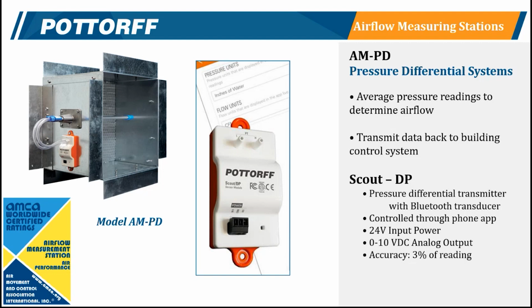So with some of our other models, they either have to be controlled through an access panel, whereas if this is up in a ceiling or someplace where access is limited, or up in something that would require a ladder to get to, like above a drop ceiling, you can do that through your phone through the Bluetooth app. Now you still have your standard 0 to 10 volt analog output, so you're not going to get an output signal through the Bluetooth app going to the BMS, which is not very common.